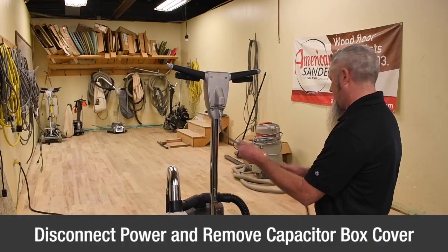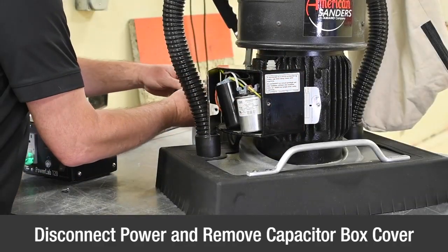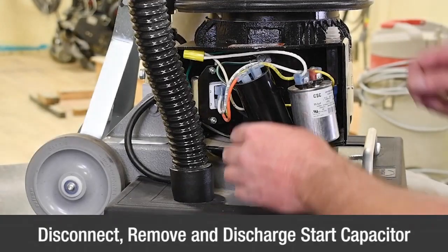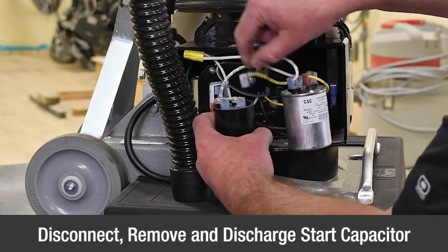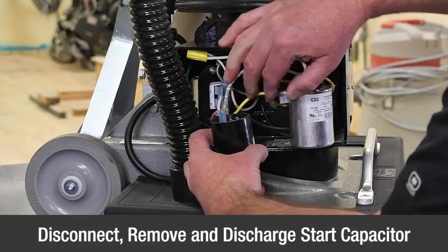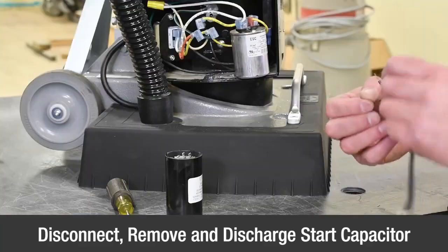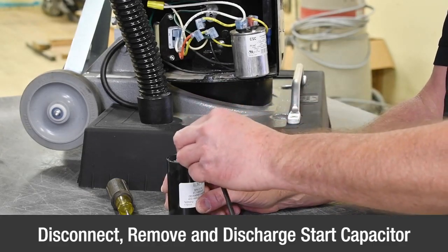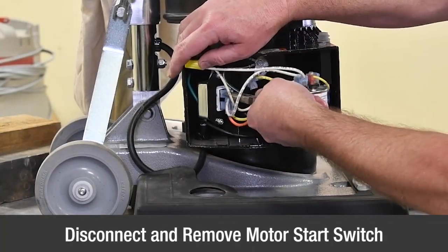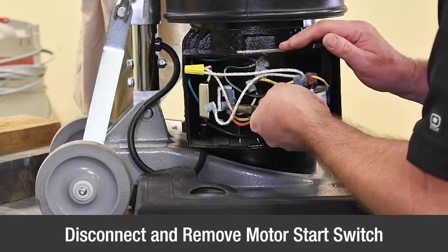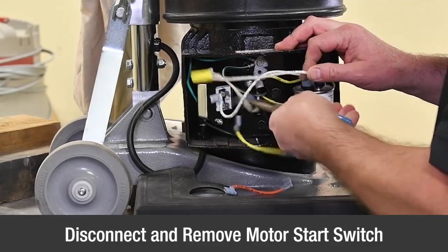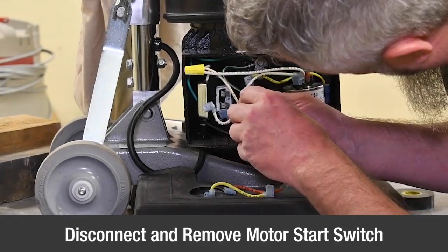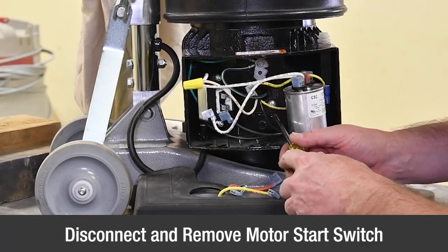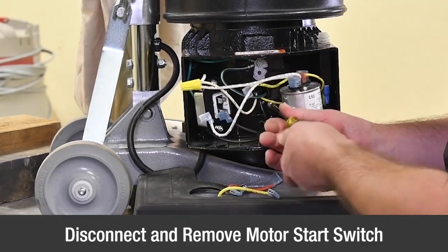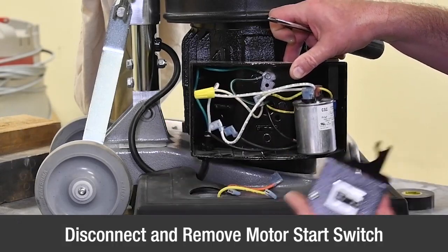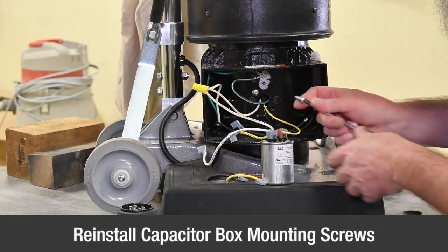Disconnect power from the machine and remove the capacitor box cover. Disconnect and remove the start capacitor as described previously. Be sure to discharge the capacitor for safety. Disconnect and remove the motor start switch. The old-style start switch is mounted with 2 screws that also secure the capacitor box to the motor. Then reinstall the capacitor box mounting screws.